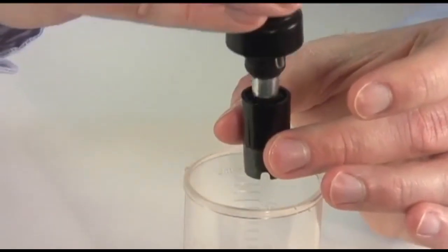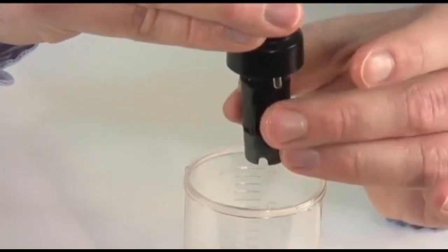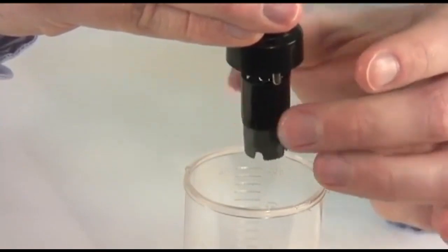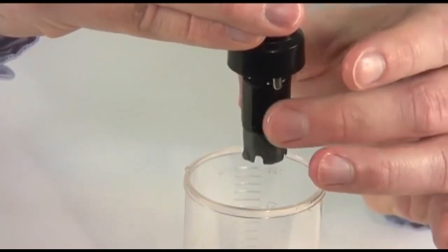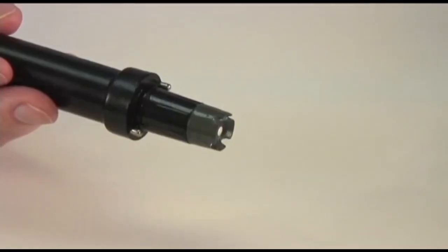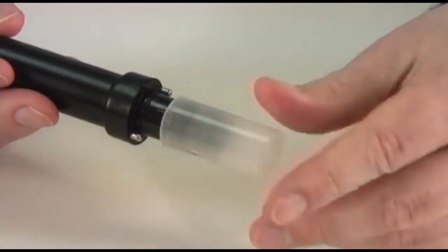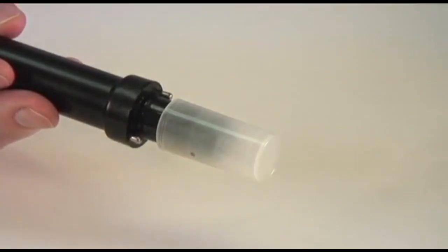Step 7. Now, with the sensor facing downward, slowly screw on the membrane cap upward and counterclockwise. Some electrolyte will overflow, but that's okay. Step 8. Finally, put the protective plastic cover on the probe. You're going to want to use this while the probe is not in use. It keeps it safe and in good condition.